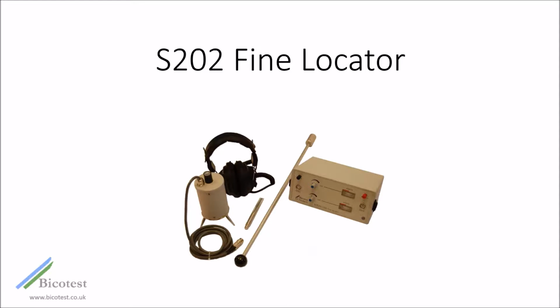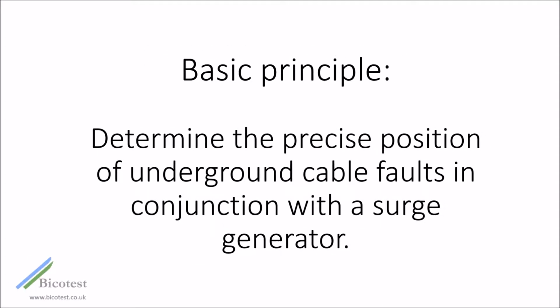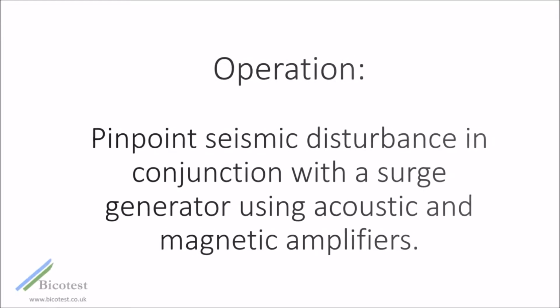The S202 fine locator is an easy to use dual channel detector and amplifier specially designed to determine the precise position of faults on underground cables in conjunction with a surge generator or capacitor discharge set. The instrument is used to locate cable faults by pinpointing the seismic disturbance created by the energy from a surge generator arcing over at the fault, either between conductor and cable sheath or between two conductors. A sensitive pickup detects this seismic disturbance, which is then amplified and indicated to the operator both audibly on headphones and visually on a display meter.